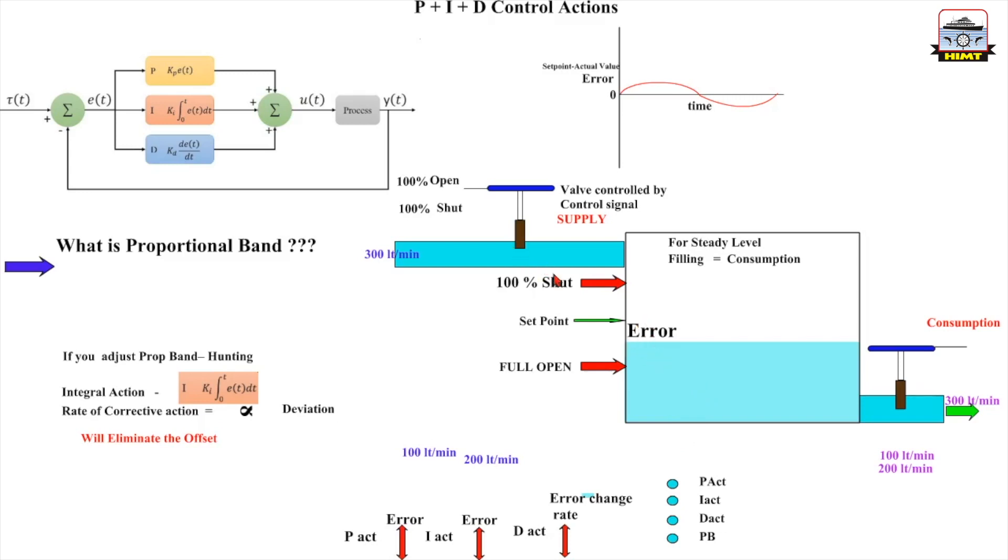Because of the proportional action, the valve started opening and here I got a steady state, but I got an error offset. Now I want to eliminate the offset. How can I eliminate the offset? By making sure that the valve is opening more. This is exactly what the integral action is going to do.